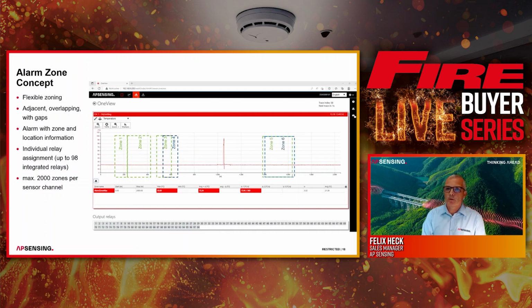We can also have completely overlapping zones. For example, if you want to create a pre-alarm and a main alarm, this can be done by completely overlapping zones. Zone 5, for example, is more sensitive and informs, for example, the facility manager. And zone 6, if this alarm comes out, then the fire brigade will be called. And if at a certain position, for example here, the heat increases, the heat increase will be measured, the alarm characteristic at this position will be exceeded, we will trigger an alarm. And if an alarm is triggered here, then, for example, one of our 98 relays in the controller will be triggered, and this will then show the exact position for the fire brigade to go there and extinguish and deal with the fire.